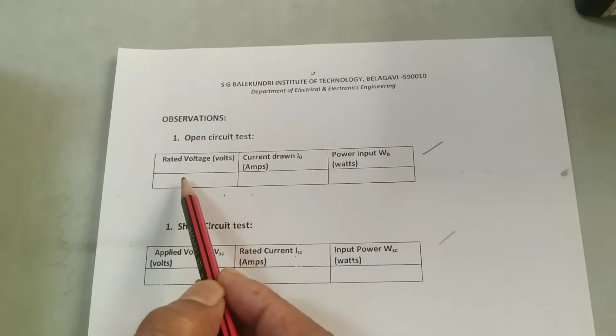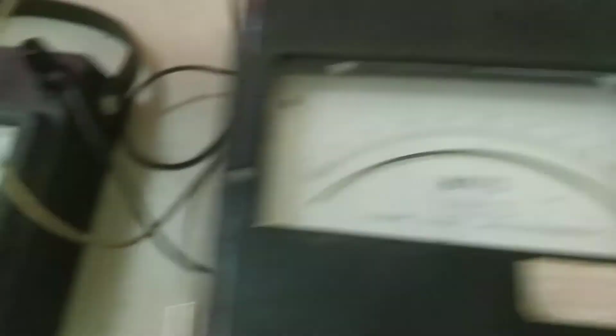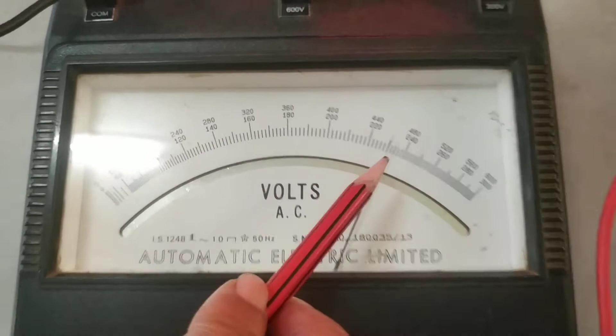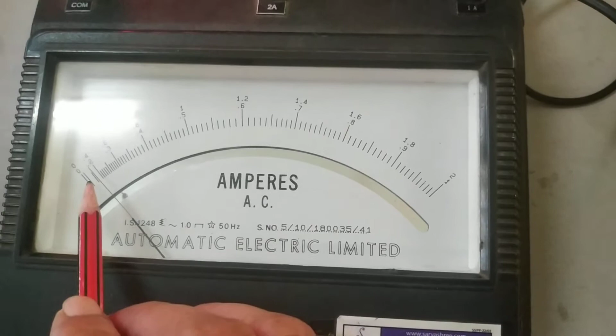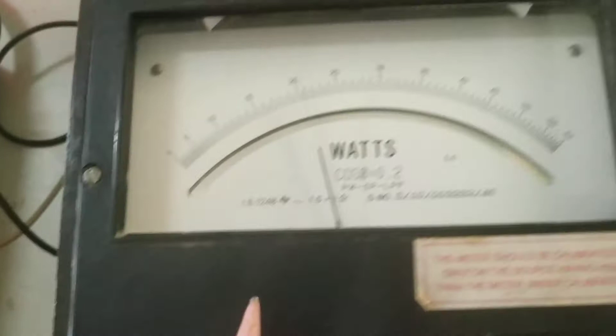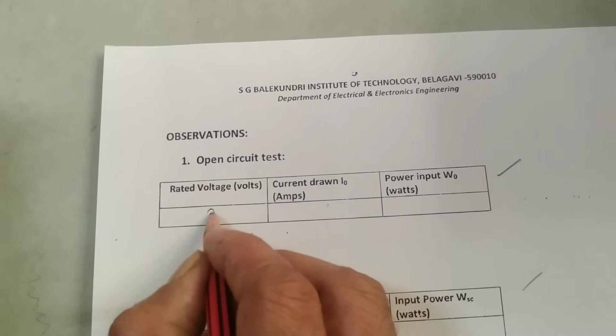You can see here the observation table. For the open circuit test, we need to take the voltmeter reading, ammeter reading, as well as the wattmeter reading. First the voltmeter reading, which is 230 volt, and for current we are using the 0 to 1 ampere range, so we need to read the lower scale. It is about 0.2 amps. The wattmeter reading is 21 watt. These readings are put in the observation table: voltage is 230 volt, current is 0.2 ampere, and wattmeter reading is 21 watt.